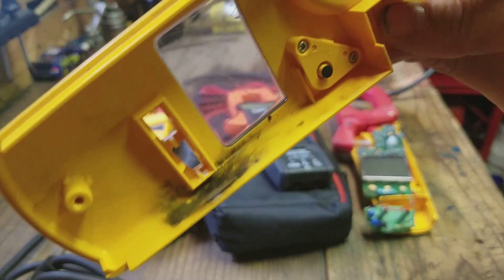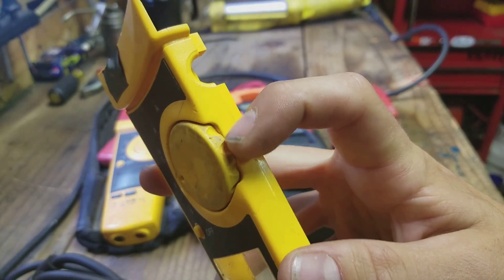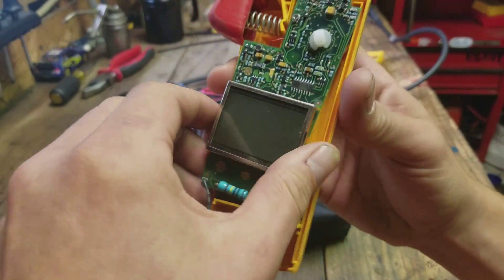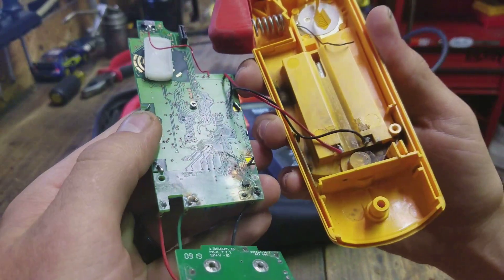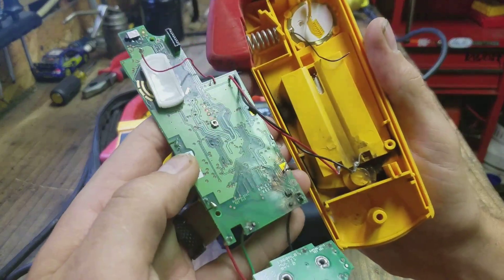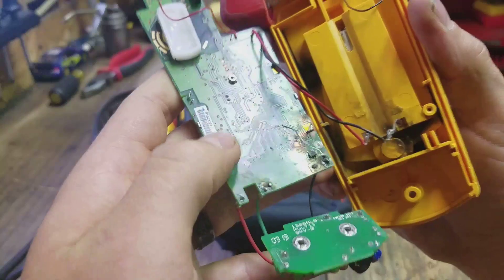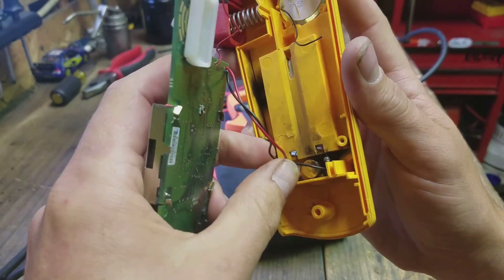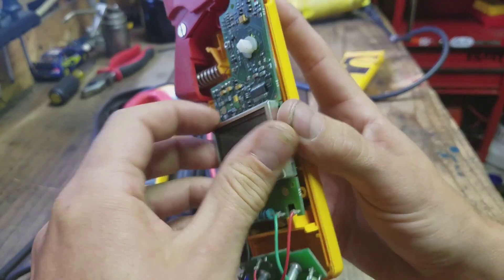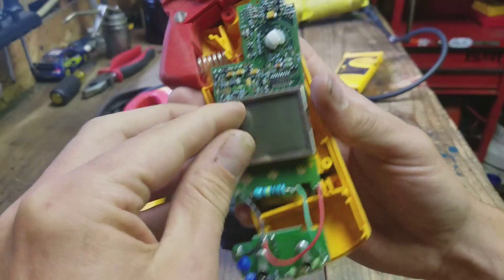The last pair: I went to test some 208 volts and it went boom — a fireball shot out of the gap where the selector wheel is. I tested 120 on all three phases on a 120/208 panel, and then when I went to check the 208s, it blew up in my hand, scared the hell out of me. I think what happened was a little plastic protector that shielded the battery connections from the board got a hole in it, and I effectively ran 208 volts to some AA batteries.